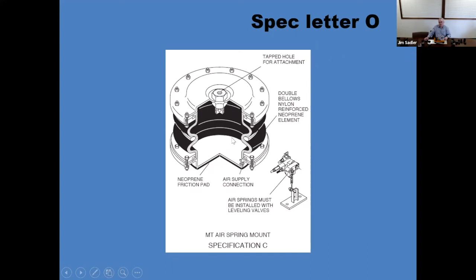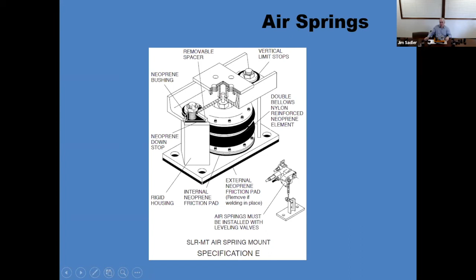For seismic zones, we can put that same air spring in a housing. And again, now we've orchestrated the isolation and the seismic restraint, where we have that conflicting engineering requirement. But when we put that air spring in a housing, we've got both the isolation and the seismic restraint covered. This restraining assembly is designed so it's not in contact during normal operation. But like the snubber, should the equipment move, this housing will keep the equipment in place.